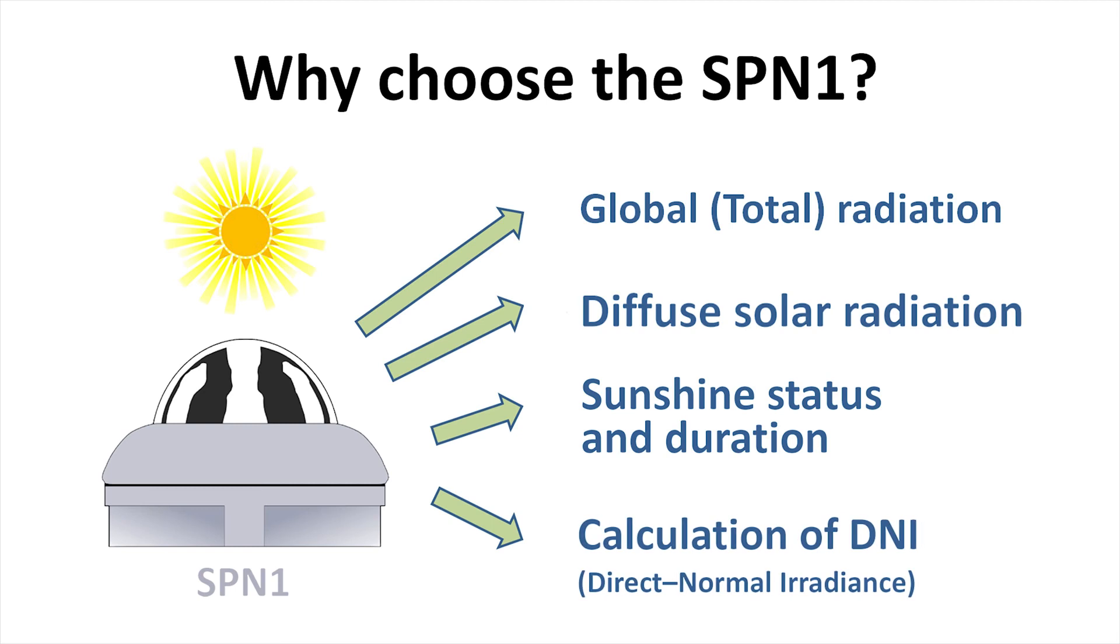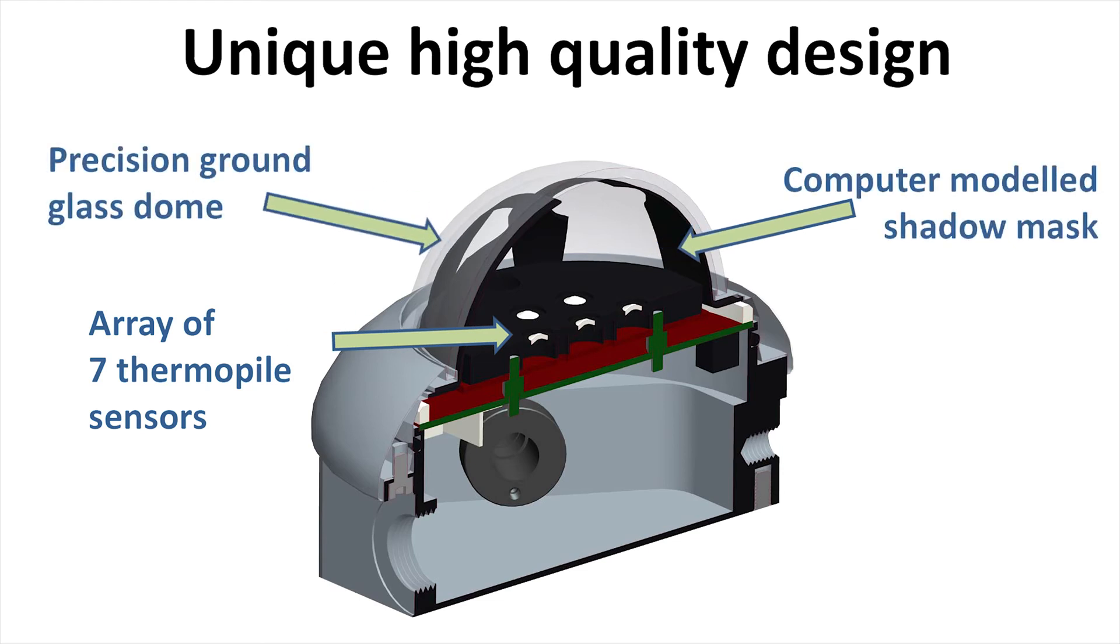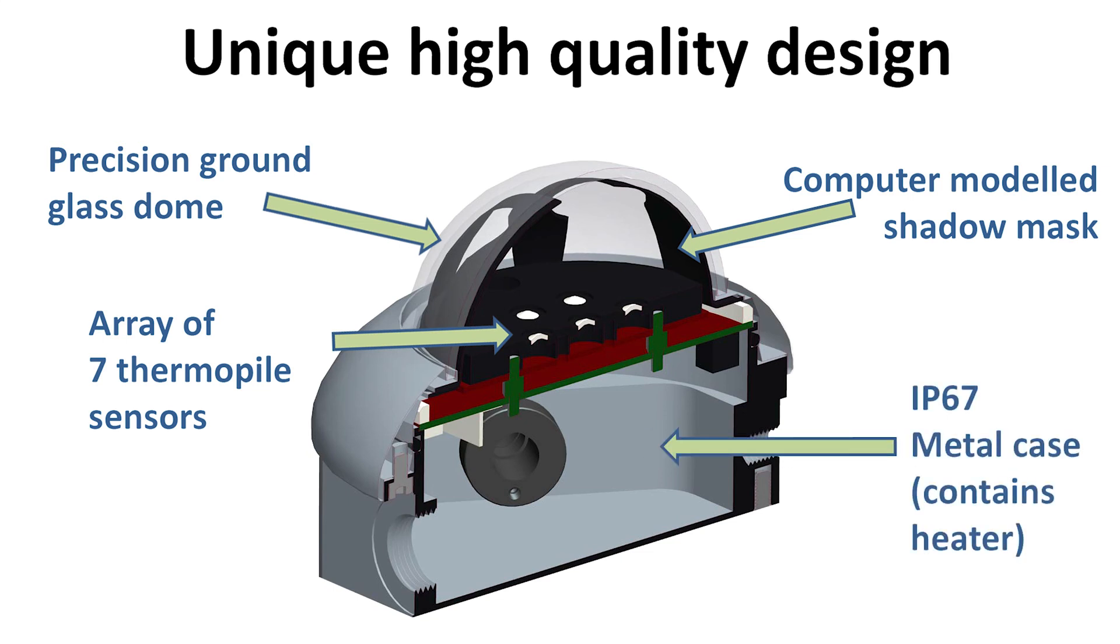It enables calculation of DNI – direct normal irradiance. Its innovative design features seven thermopile sensors, a computer-modeled shadow mask, a precision ground glass dome, a robust machined aluminum case, and an internal heater.